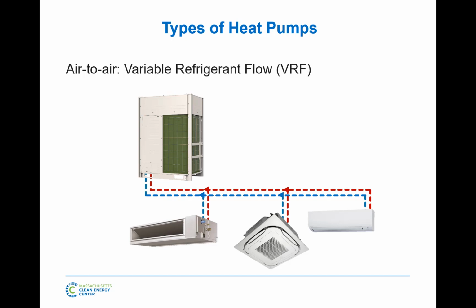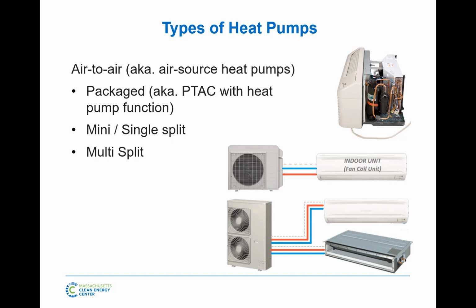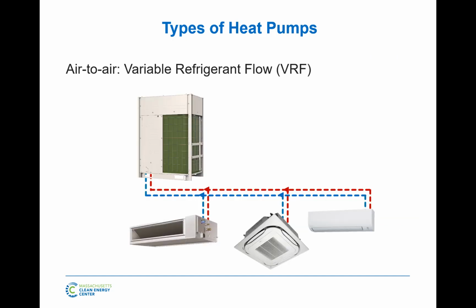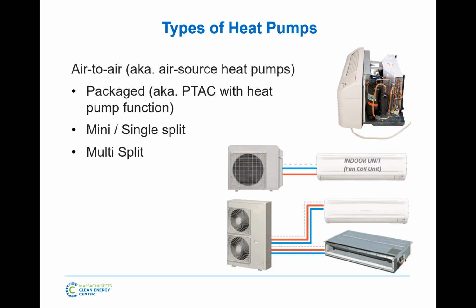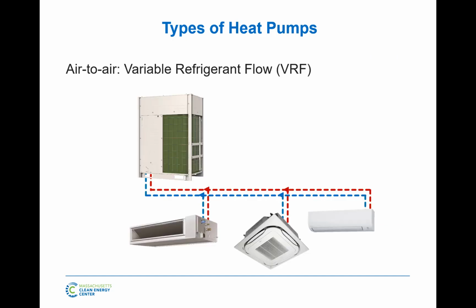Now, a big difference between a multi-split and a VRF, because the VRFs also come in smaller machines. They also come in machines that look like this one. A multi-split is home run piping. So every unit is piped back to that outdoor unit. So they're limited to maybe 4 or 5 units, and they only go up to about 4 or 5 tons of capacity. Call it a big house kind of thing. Well, big is relative, a few thousand square feet. With anything VRF, everything is in series, which means I take pipes, I go into the building, and from there I'm going to tee off and feed all sorts of indoor units.